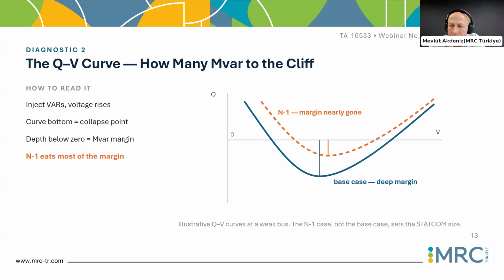So this dynamic reactive support can be supplied by the synchronous generators, which are already available in most of the grids, mainly hydraulic power plants or thermal power plants. And once we add, or replace the thermal powers with, new IBR type machines, we should also check the dynamic reactive power support of these machines, as I mentioned in the beginning, not only on the data sheets or capability, we should also check the commissioning tests or design documentation, or even in real faults, we may check whether these responses are enough or not, or if they are capable of giving their contribution specified in the data sheet.